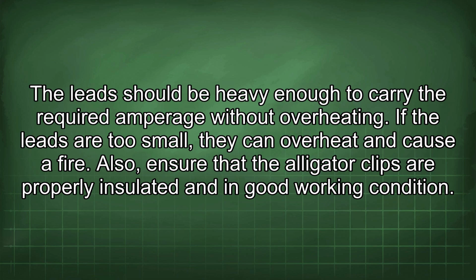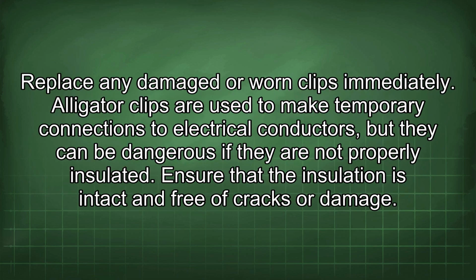Also, ensure that the alligator clips are properly insulated and in good working condition. Replace any damaged or worn clips immediately. Alligator clips are used to make temporary connections to electrical conductors, but they can be dangerous if they are not properly insulated. Ensure that the insulation is intact and free of cracks or damage.